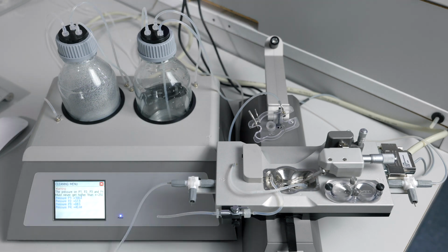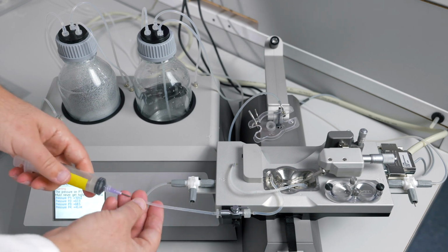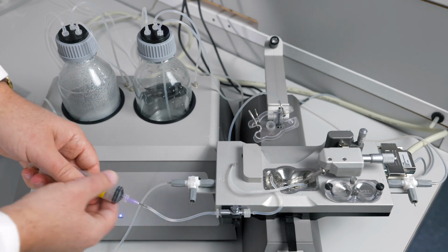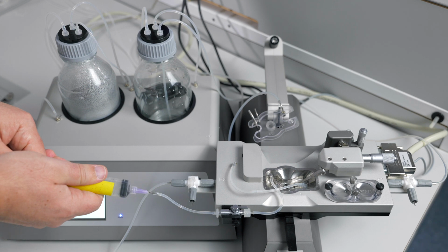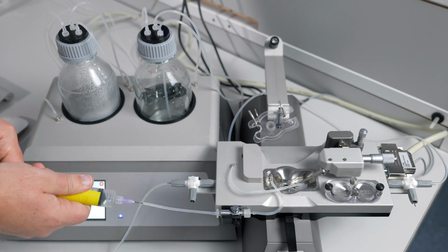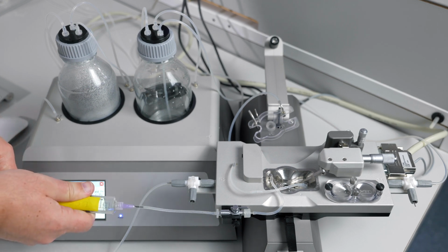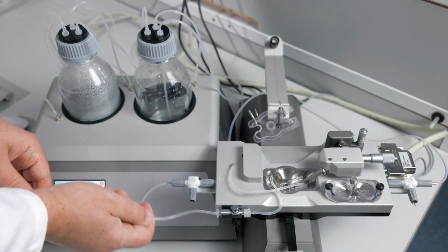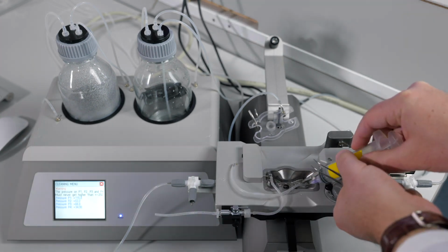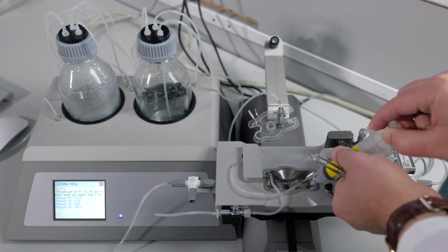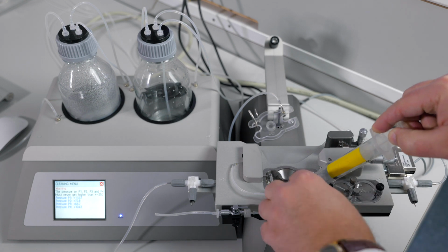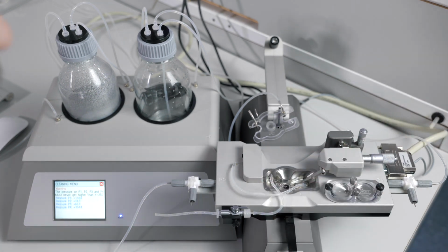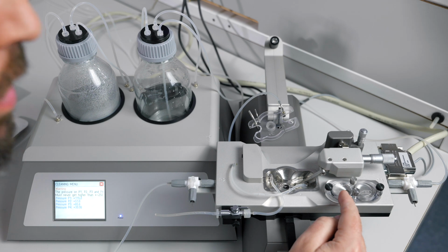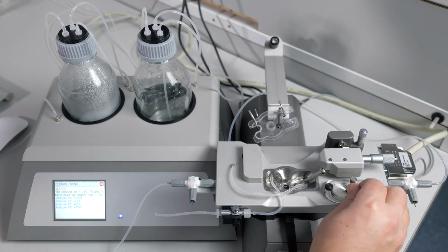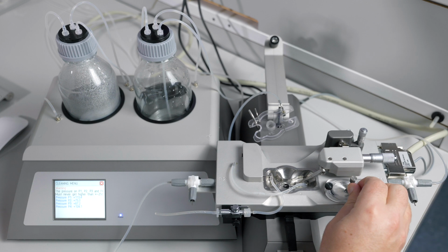Now that we have air only in the chamber, we will draw the air through the P2 cannula line first, and then P1. This will remove all the water and any leftover salt from the lines. Repeat this process on the P1 cannula. You can see that P1 and P2 wells are emptying. We will open these valves to make this go faster.